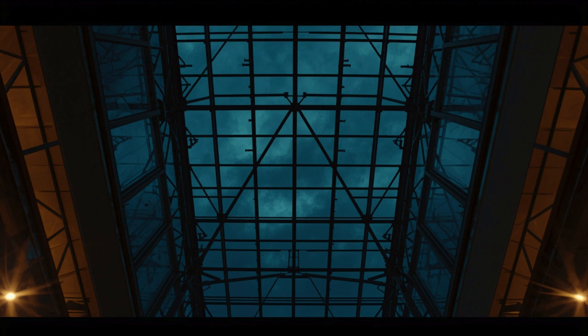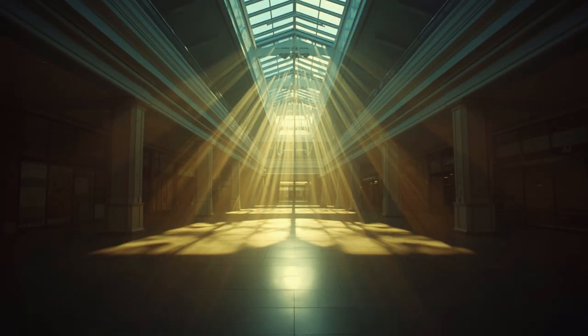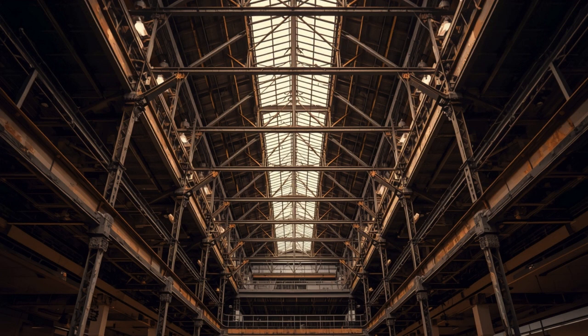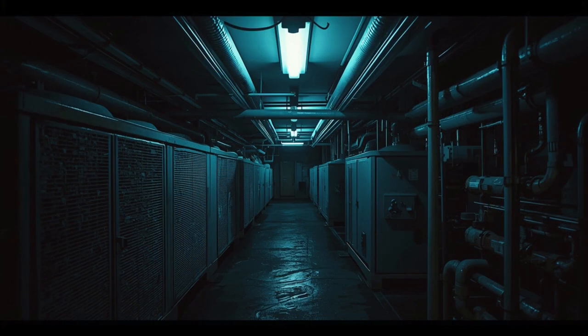The atrium eliminated these separations for the floors facing the central void. A fire starting on the ground floor of an atrium, or spreading smoke from a fire elsewhere in the building into the atrium void, could expose all floors simultaneously to smoke and potentially to fire. The vertical chimney effect of the tall, open space could accelerate the upward movement of hot gases with alarming speed.